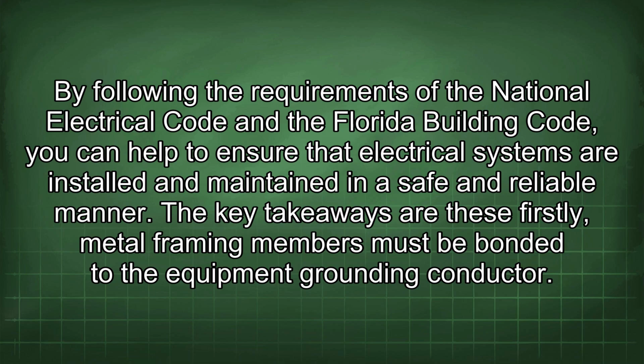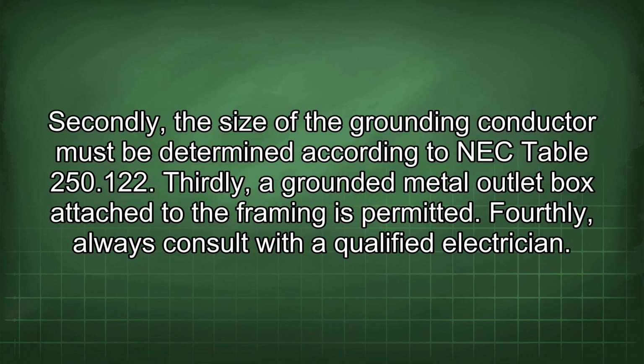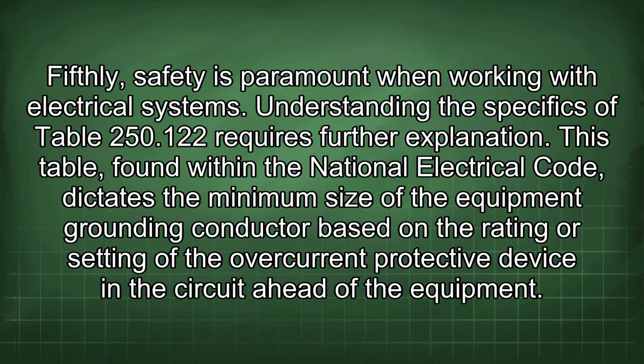The key takeaways are these: firstly, metal framing members must be bonded to the equipment grounding conductor. Secondly, the size of the grounding conductor must be determined according to NEC Table 250.122. Thirdly, a grounded metal outlet box attached to the framing is permitted. Fourthly, always consult with a qualified electrician. Fifthly, safety is paramount when working with electrical systems.